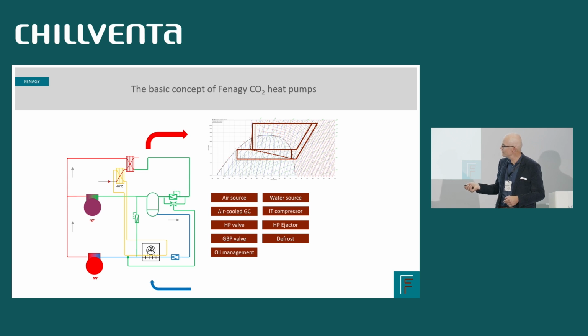The ejector is lifting flash gas into the receiver, and then the IT compressors or the parallel compressors are compressing vapor from the receiver up to the same pressure level as the MT compressors down here. So that is the basic CO2 cycle. You will find the same kind of cycle in a supermarket, just a much smaller system, of course.